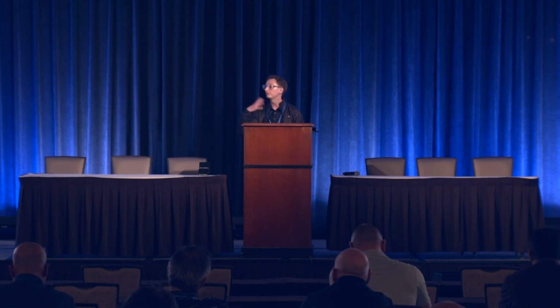That's a really great question. I think it just depends on the process. The way I think most Raman companies do it—and I know this is our strategy—is we'll start building the models for an online process even before the analyzer is brought to that site to be installed. We'll have them give us samples from their online process, run it on our instruments, help build the model beforehand, and transfer it onto their analyzer so that when we do the commissioning or installation, we can immediately start getting results. They might not be exactly perfect, but the combination of what we did beforehand with the commissioning, plus collecting samples within the first day or two after installation, gives us the ability to start getting accurate results within just days of the commissioning. So I think that's probably the strategy that works best.